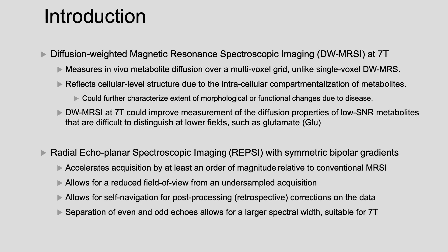The imaging is achieved with radial echo-planar trajectories using symmetric bipolar gradients. This allows for an acceleration of the imaging time relative to conventional MRSI. It also allows for achieving a reduced field of view acquisition from an undersampled set of spokes. And importantly, it provides a capability for self-navigation, which is important for doing corrections on the data. Another important feature of symmetric echo-planar spectroscopic imaging is that the even and odd echoes can be separated in order to achieve the larger spectral width, which is important for 7T.